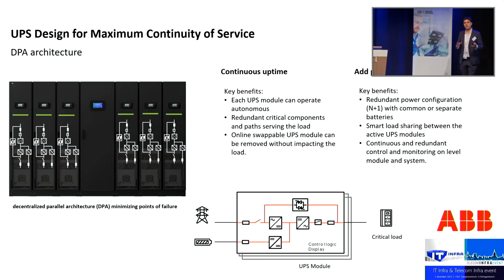So I don't want to have a UPS which might have a single point of failure, which would jeopardize the operation of the whole UPS. So I need to think about every single part of the UPS. We were speaking about the bypass, so I don't want that my bypass is a single point of failure. I want to think about the communication between the devices and not to have maybe a master which would control. So all the modules of the UPS should be capable to be a master or take over, right, the whole logic. Good idea is also to have, for example, hot swappable UPSs. So in case that I need to do the maintenance on one of the modules, still I can keep running all the other modules to have the real N+1 redundancy. So typically we start thinking about the components from the UPS side and to select the proper UPS for the reliability.